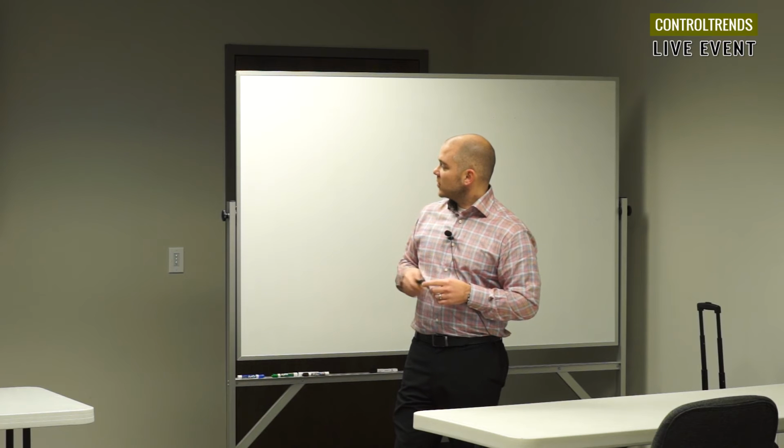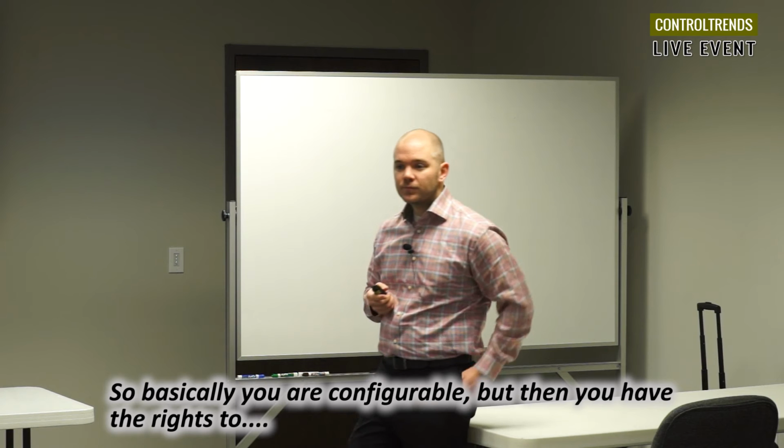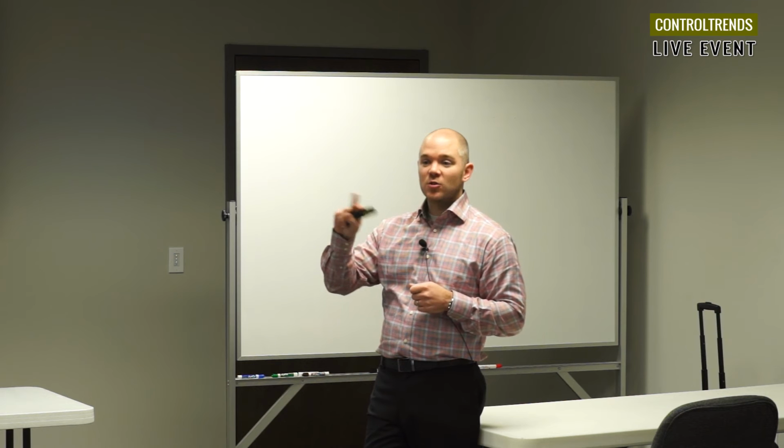The Unitary controller is basically configurable, but then you have the right to customize. Yeah, you could start with our application and then customize from there. You could take our application completely out, make it plain vanilla, and build everything out yourself. All the programming is programmable. The content you display on the wall sensors is still all programmable. So if you have an OEM application or a custom application for one of your integrators, you can put custom things in that NetSensor, so now he can set his own points through that interface. Okay.